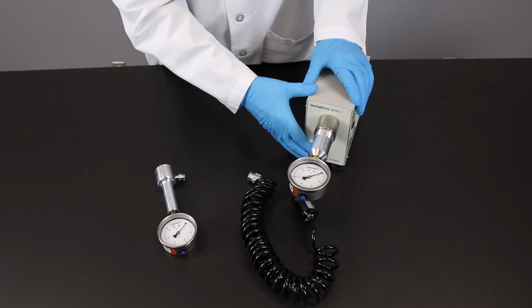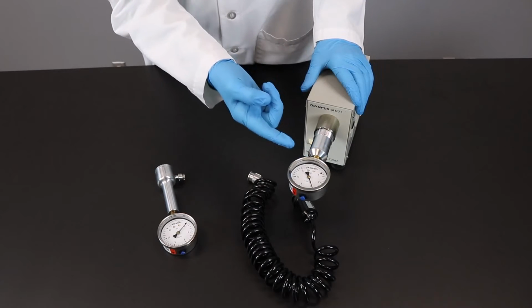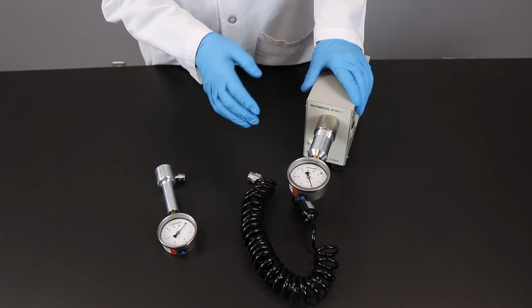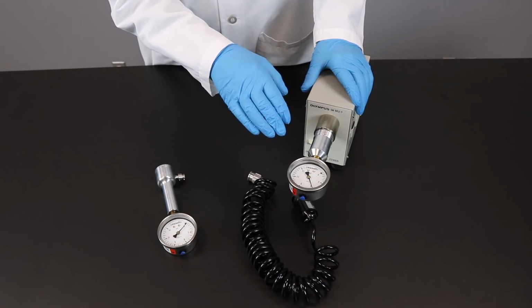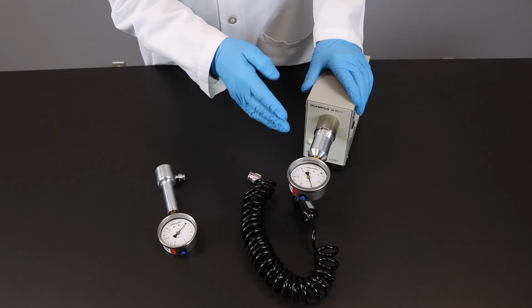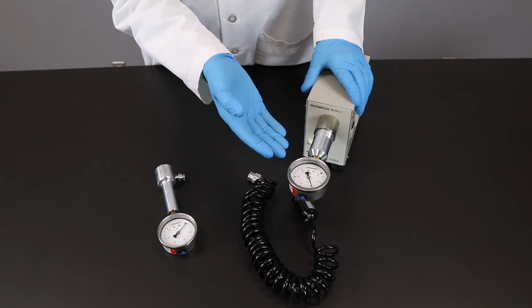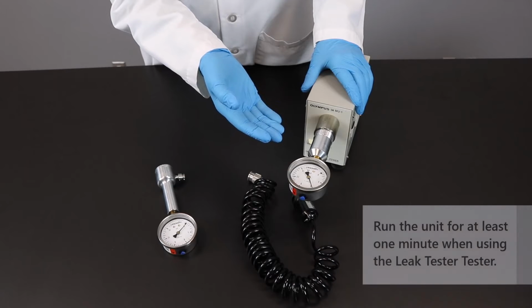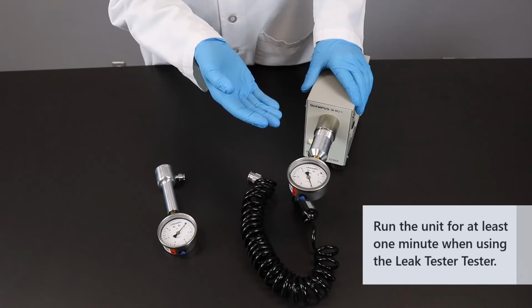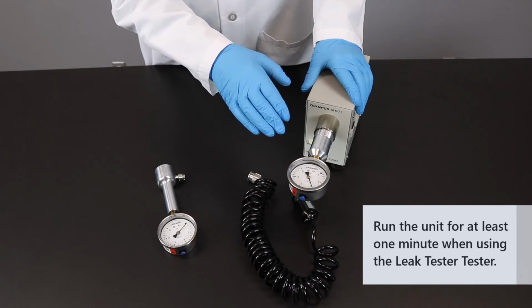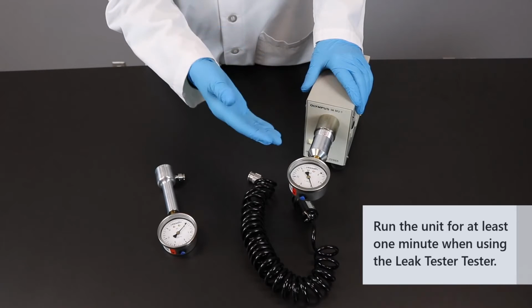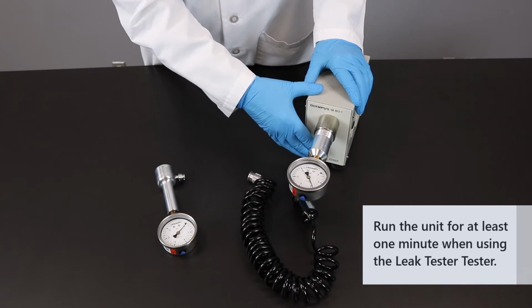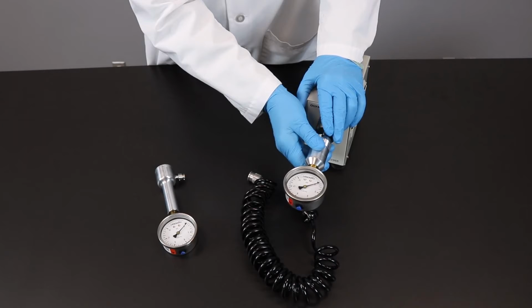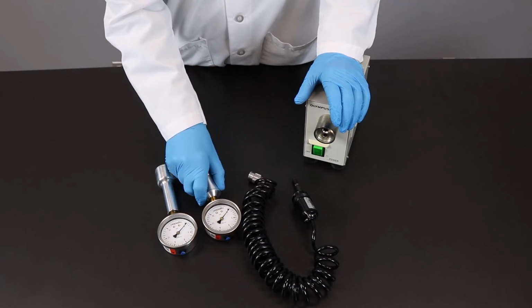We're going to turn on the base unit and look for the pressure reading on the gauge. This reads in pounds per square inch, or PSI. It needs to be at least 4 PSI, and you can see on this gauge it reads almost 6. So this passes. When you perform leak tester verifications, you need to do this for at least 1 minute. We'll say that 1 minute has passed. We turn the leak tester off, and we remove the leak tester.